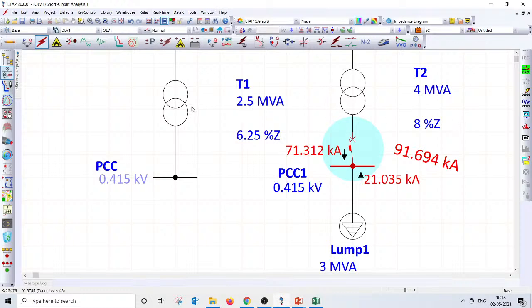I have seen quite a lot of consulting organizations working in steel plants limiting the maximum transformer rating to just 1.6 MVA. They will never allow you to go beyond 1.6 MVA. It has grown to 2 MVA in some industries, and typically, as Parthiban and Vaishya have answered, 2.5 MVA. That's the Indian mindset, in most places we go with a maximum transformer rating of 2.5 MVA, and I guess other countries like Singapore or even the Middle East go with the same standard rating of 2.5 MVA in most cases.